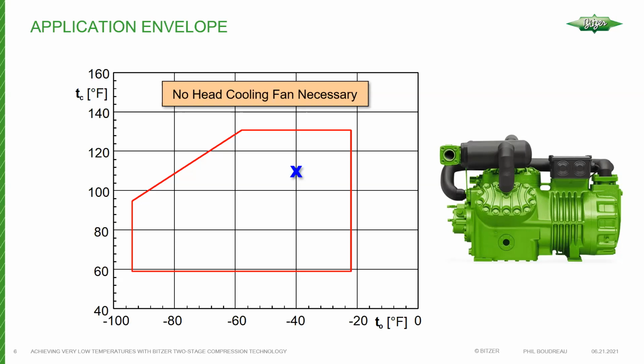You're basically at the top, getting close to the top end, if I can say that, for a two-stage compressor with lots of room to go in terms of saturated suction temperature. You can go down to, like I said, almost minus 90 Fahrenheit saturated suction temperature or so, depending on what your saturated discharge temperature is.